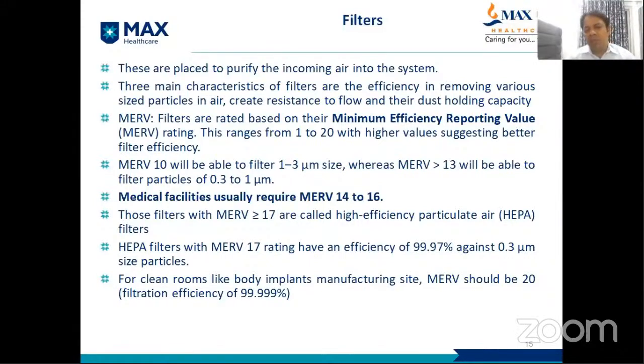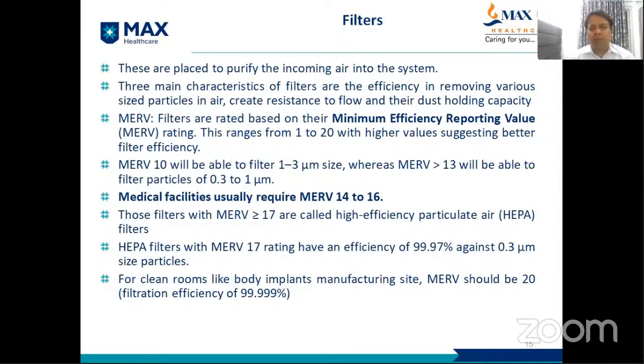Medical facilities usually require MERV 14 to 16. Those filters with MERV more than 17 are called HEPA filters. HEPA filters with MERV 17 have an efficiency of 99.97% against 0.3 micron size particles. For a clean room, like a body implant manufacturing site, where body implants are manufactured, the MERV should be 20 filters. MERV 20 filtering efficiency is 99.999%.